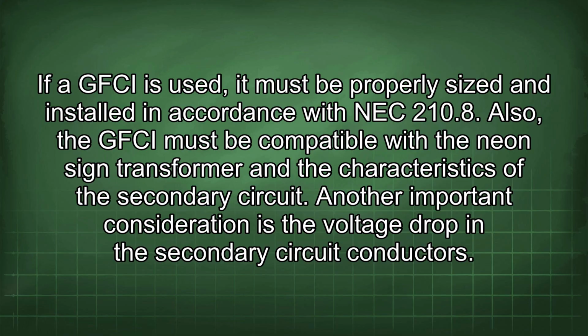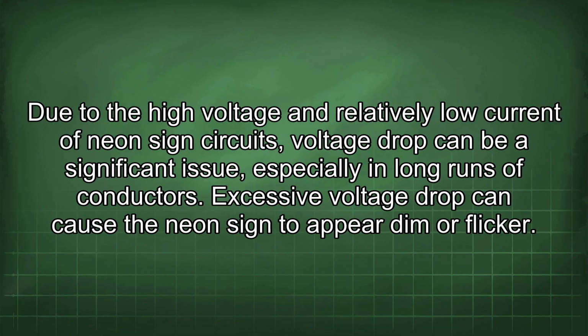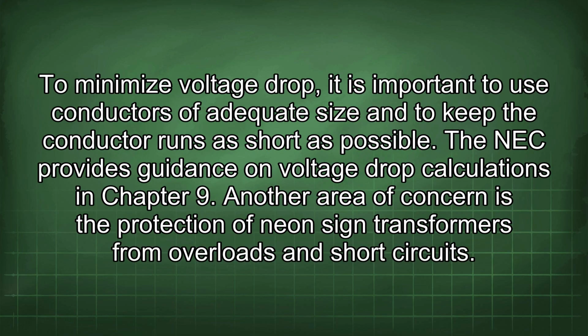Another important consideration is the voltage drop in the secondary circuit conductors. Due to the high voltage and relatively low current of neon sign circuits, voltage drop can be a significant issue, especially in long runs of conductors. Excessive voltage drop can cause the neon sign to appear dim or flicker. To minimize voltage drop, it is important to use conductors of adequate size and to keep the conductor runs as short as possible. The NEC provides guidance on voltage drop calculations in Chapter 9.